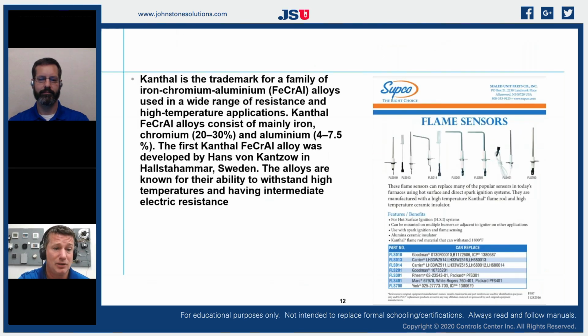When we look at the construction of a flame sensor, we would expect it to be very complicated and doing a lot of work. It's not. It's made of Kanthal. Kanthal is a trademark for a family of iron, chromium, aluminum alloys. The original ones were made of stainless steel. The reason we use Kanthal is that it has a slightly higher temperature rating than our stainless steel counterparts. It can withstand a few hundred more degrees.